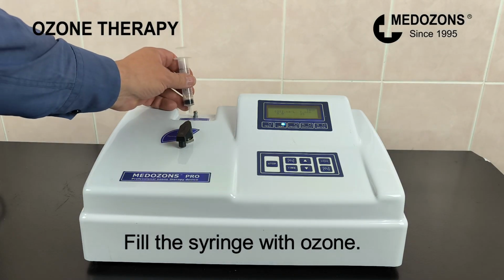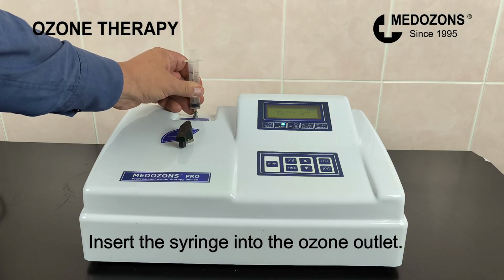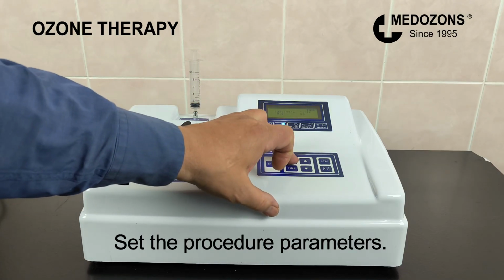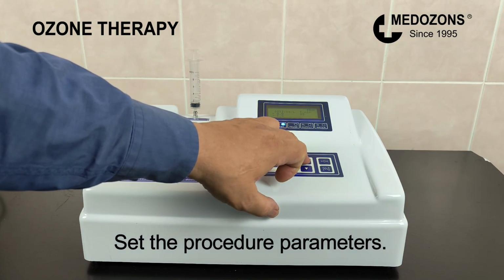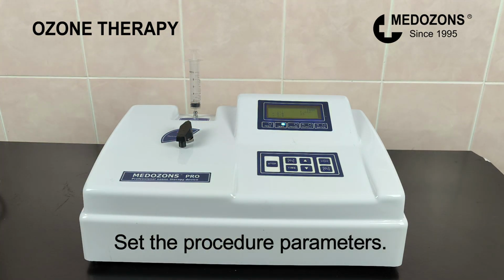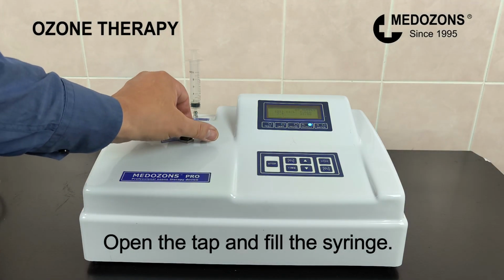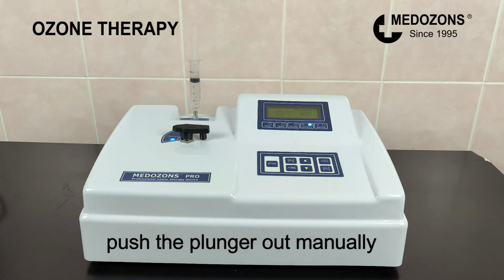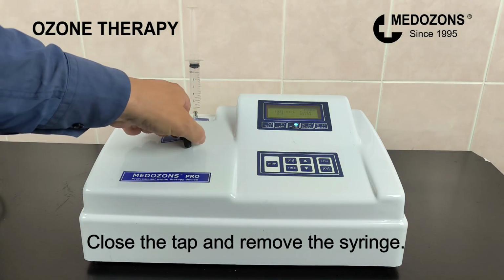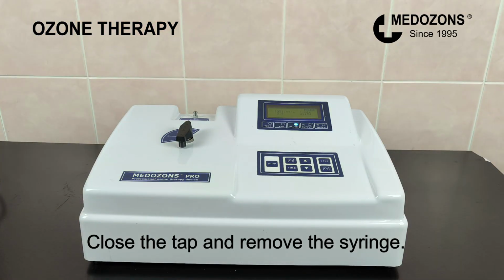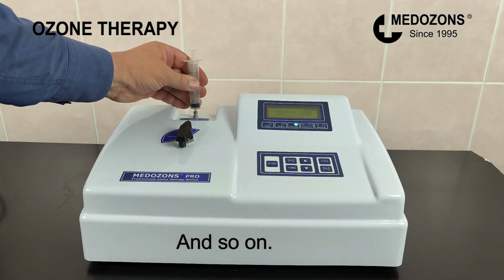Fill the syringe with ozone. Insert the syringe into the ozone outlet. Set the procedure parameters. Open the tap and fill the syringe. If the syringe is tight, push the plunger out manually. Close the tap and remove the syringe. And so on.